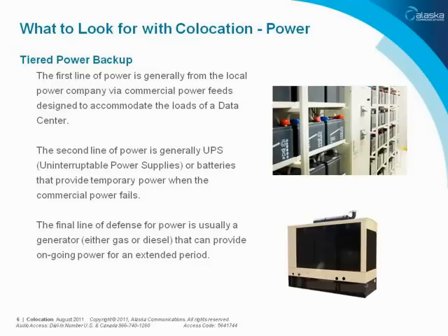You also want to investigate the size of the generator fuel tanks and what the refueling plan is. People out on the East Coast recovering from Irene right now, some are only losing power for half a day, 12 hours. Some will be without power for 24, 36, even 48 hours. You want to make sure that if you've gone to the expense and trouble of planning to use a data center, it has a sufficient fueling plan to maintain its power and keep those generators running.